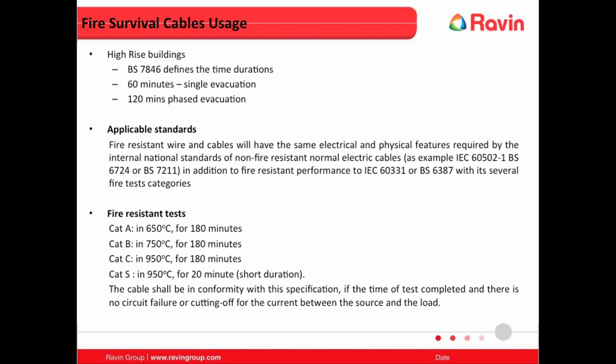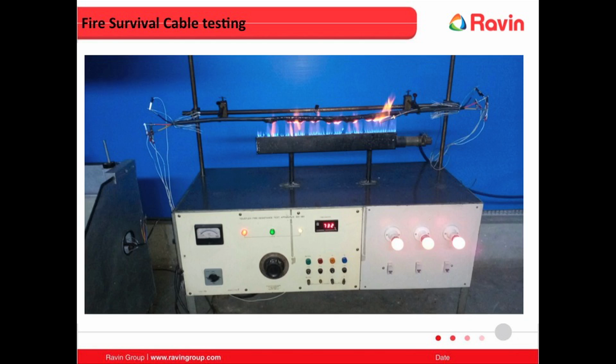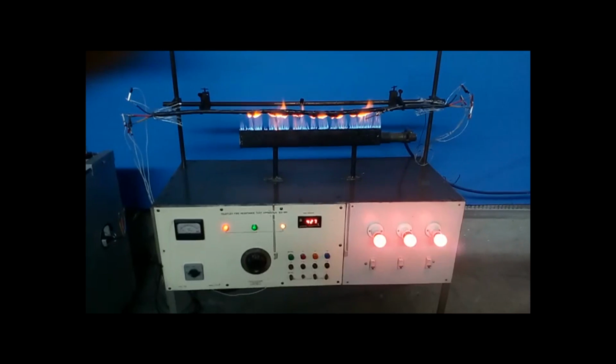Depending on the kind of structure and the application, there are various categories of fire survival cable which are put to use, from 650 degrees to 950 degrees. The equipment shown is capable of testing fire survival cable for a period of 3 hours.